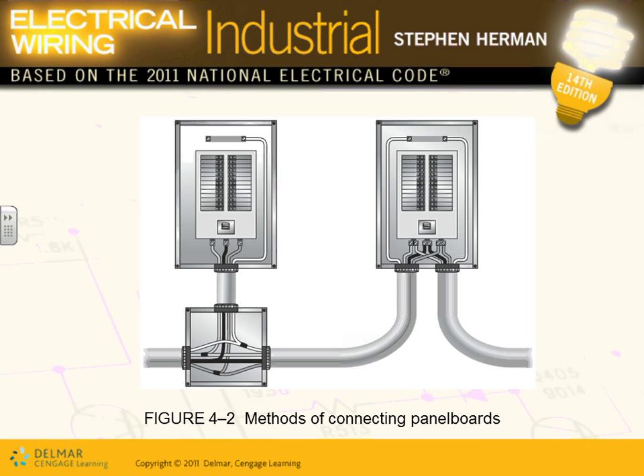What happens if they have a short circuit right inside this panel? How many panels are you going to lose? All the panels on this feeder could be lost. So what they did here is one design. The way we're going to design it is different. Our project is going to take this panel and feed it from a separate feeder, and take the second panel and feed it completely from a different feeder.